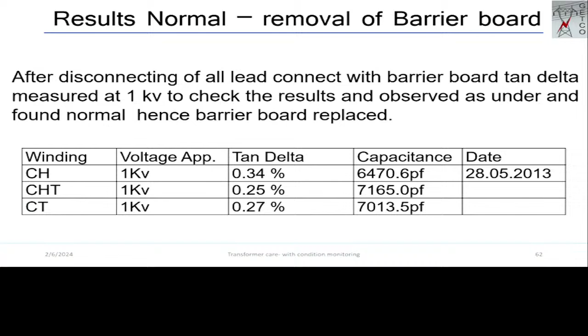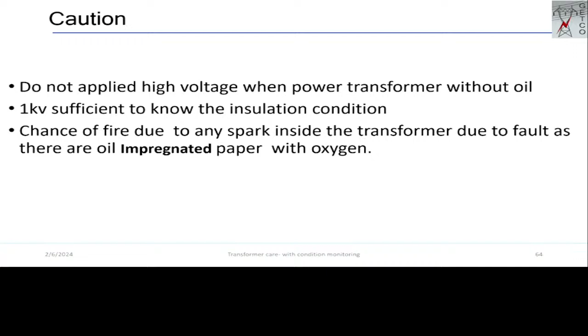So after total oil drain, transformer inspection was carried out, and you see in the barrier board we found some treeing. Okay, so we confirmed that by removing all the connections of the barrier board, tan delta taken at 1 kV, and the result was found normal. So it is confirmed that there is an issue in the barrier board. So the barrier board was replaced and the transformer put into service.